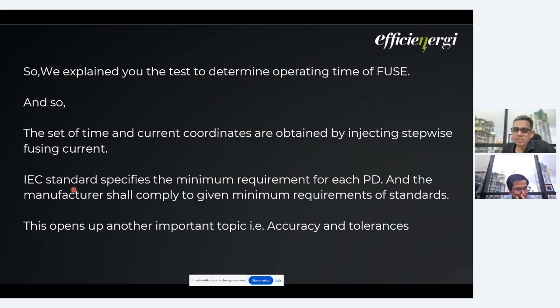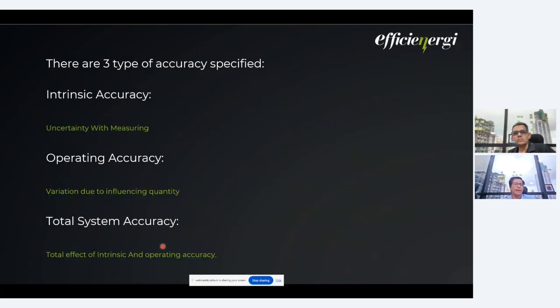Or any PDs for that. Each manufacturer will have a different manufacturing process, and there is a possibility of tolerances. Each and every fuse series may not have the same operating time. So the IEC standard specifies the minimum requirements for each protecting device, and the manufacturer shall comply with all the given minimum requirements of the standards. Now this opens up another important topic, that is accuracy and tolerances. There are three types of accuracies specified as per the standards.